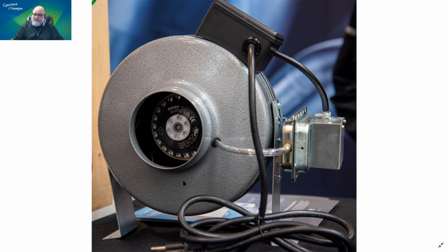This is, for example, what we call an inline fan. This is 4 inch, by the way, the diameter here is just 4 inch. So if you are running a 4 inch diameter airflow duct for a very, very long distance, and whatever pushing energy source that is at the beginning is too weak to overcome the resistance, then you can add these somewhere in the middle and they will add some push and help move the air where it is needed.